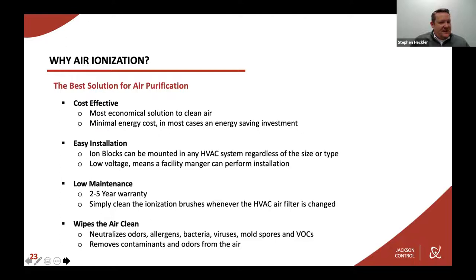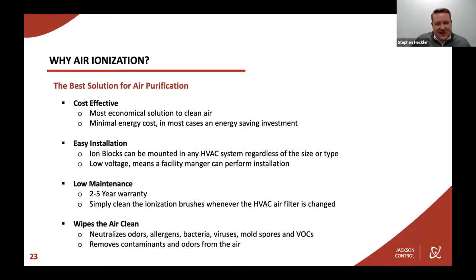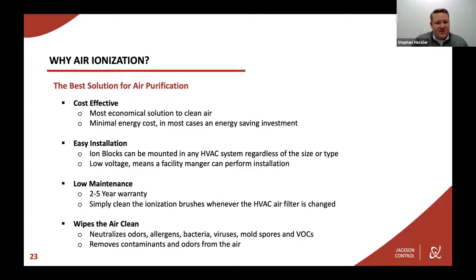What makes ionization the best solution for air purification? It is the most cost-effective. If you're going to do everything possible to make your building as safe as possible, you would do UV for surfaces, UV in the space for unoccupied times, UV in the duct, HEPA filters, ionization, and a ventilation sequence in your controls. But not everyone has that first-cost budget. Ionization can be the first thing installed — it's active immediately for people in the space. The installation is very easy. Ion blocks are very small, can be mounted in any HVAC system regardless of size or type, and are low voltage — 24 volts. You get them a signal and they will fire up.